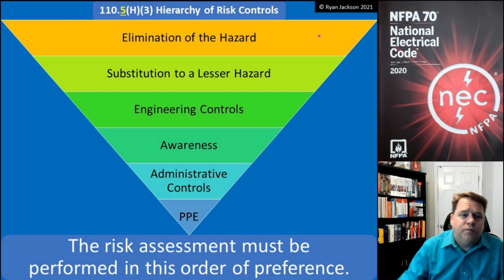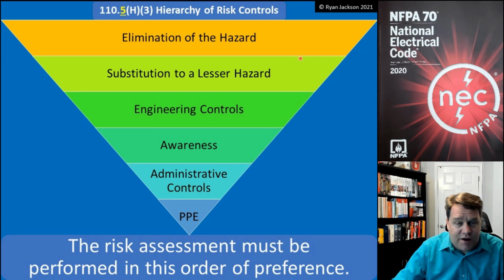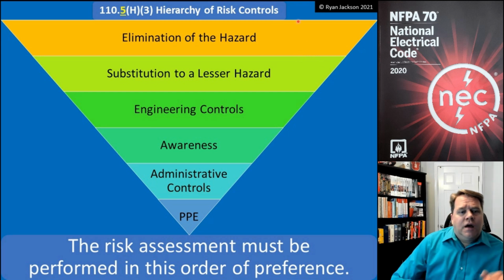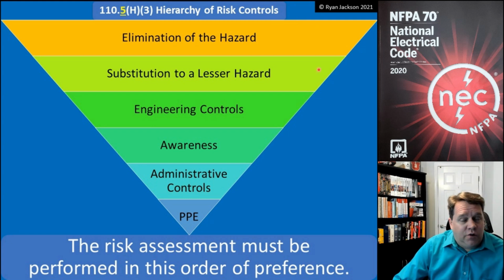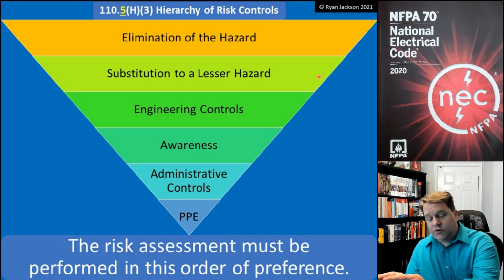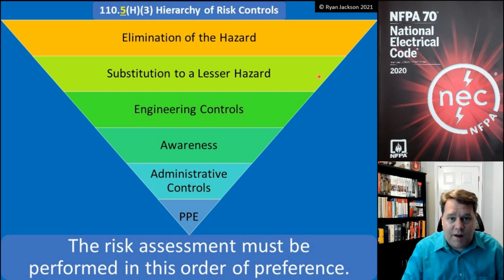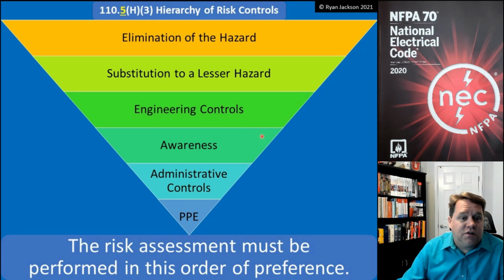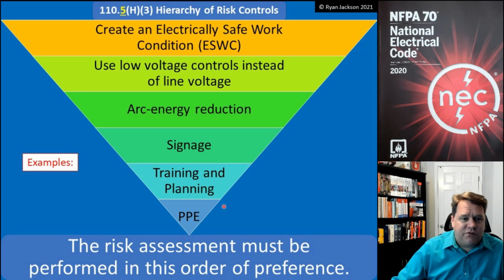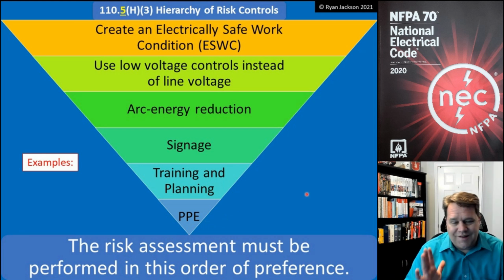So the first thing we want to do is try to eliminate the hazard, and that's what we're going to be focusing on today. If we can't eliminate the hazard, maybe we can substitute it to a lesser hazard, work on the control circuit instead of the 480 volt circuit, perhaps. Engineering controls, awareness, administrative controls, and then again, the last option would be PPE. So examples: eliminating the hazard means we create an electrically safe work condition. And again, that's the topic for today. We could use low voltage controls instead of line voltage. We could use arc energy reduction, signage, training, planning, and then again, the last option is PPE. So we want to focus on eliminating the hazard.